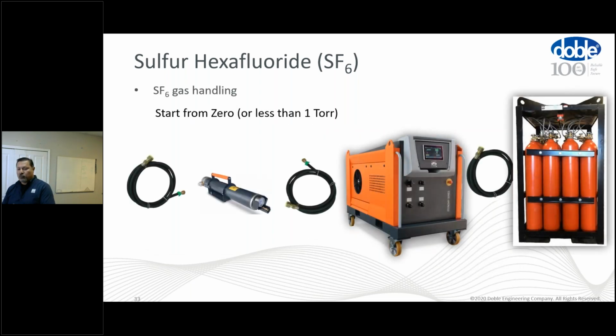Start from 0 or less than 1 torr. What do I mean here? I mean that your equipment, your tools, should be properly prepared in order to accomplish the job. If you have any SF6 or residual SF6 from either a prior job or prior handling, you're liable to cross-contaminate. You're also going to throw off any accounting that you're going to be able to do. So unless you know that you have X amount of gas in your cylinders already, and you already have a determined weight on it, you really should start with empty, under vacuum cylinders. If you're going to reuse that gas, you want those cylinders to be clean and free of any contamination.